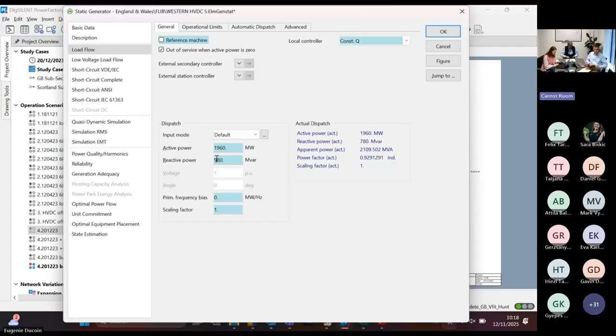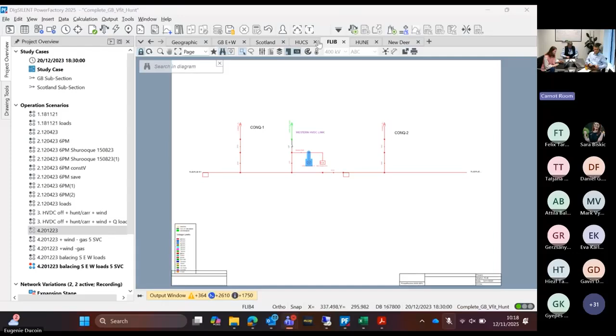Now we said, okay, let's see what happens if we increase the flow through the HVDC link and basically turn that wind farm back on, turn off that CCGT, and see what happens. So what I'm doing right now is increasing the flow through the HVDC link. And when you increase the active power flow, you also must increase the reactive power demand. And it's the reactive power demand that is creating problems for the voltage.